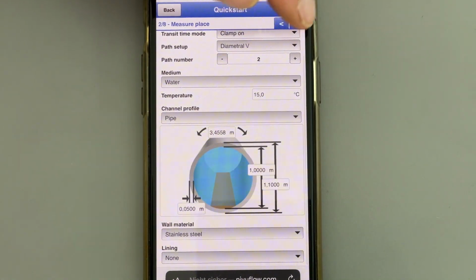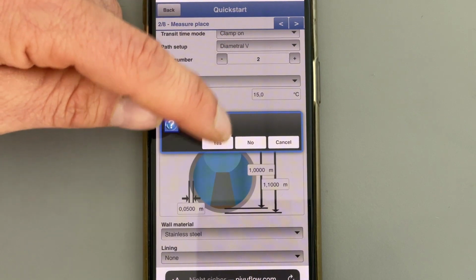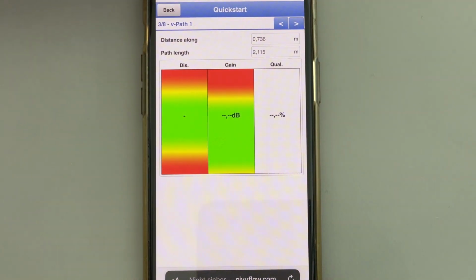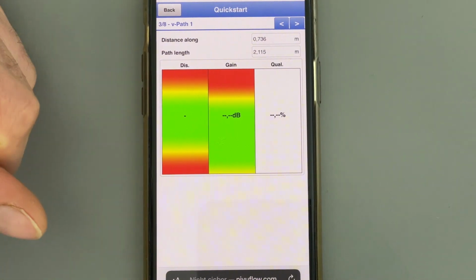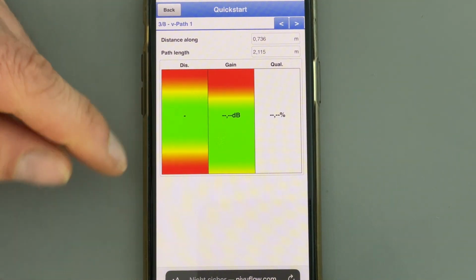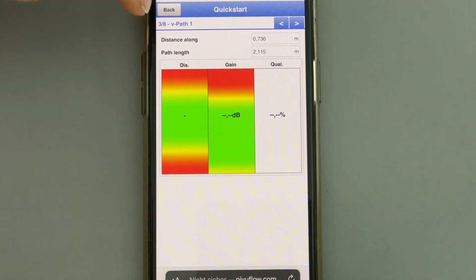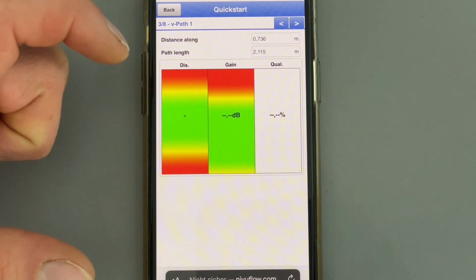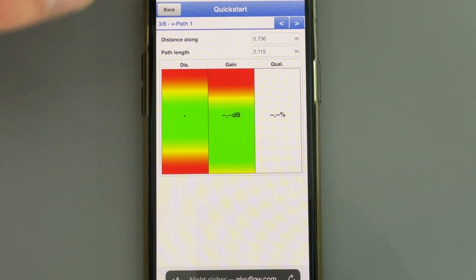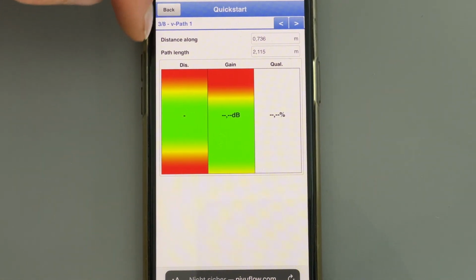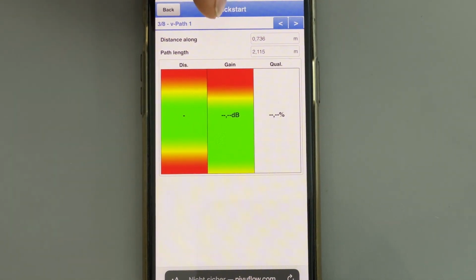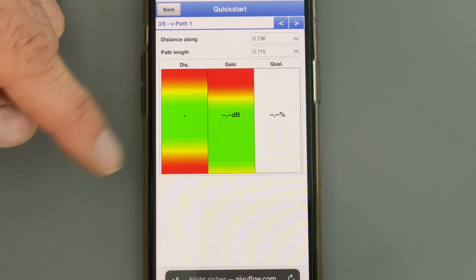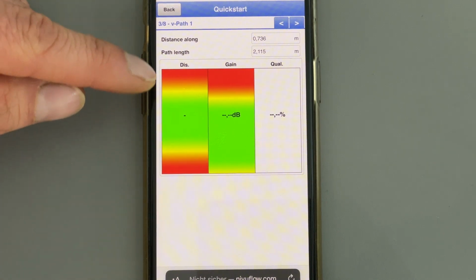On the next page, you will now get asked if you want to save the parameters. The next page you have the sensor alignment, and here in the first row it shows you the distance along. That means the spacing of the sensors on the pipe, in this case 736 millimeters, and the path length, which is not important, but is just the length of the signal traveling through the medium.